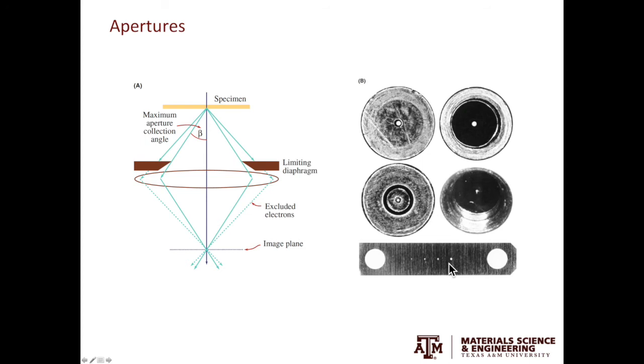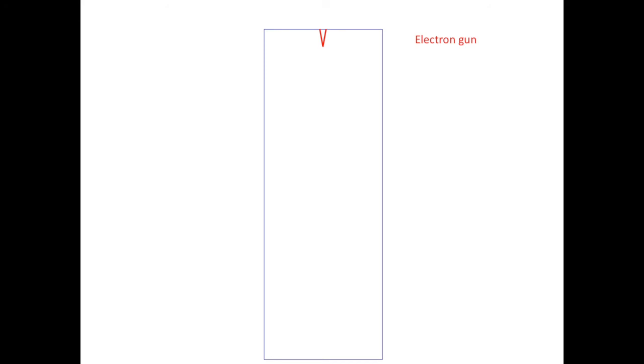With the basic understanding of lenses and apertures, we can start putting them in the hand-drawn schematic of the TEM. This is what we had from the previous video. We start with the condenser lens and condenser aperture. This will give us the condenser system. By changing the strength of the condenser lenses, you can converge or diverge the electron beam. In other words, you can change the convergence semi-angle of the electron beam.